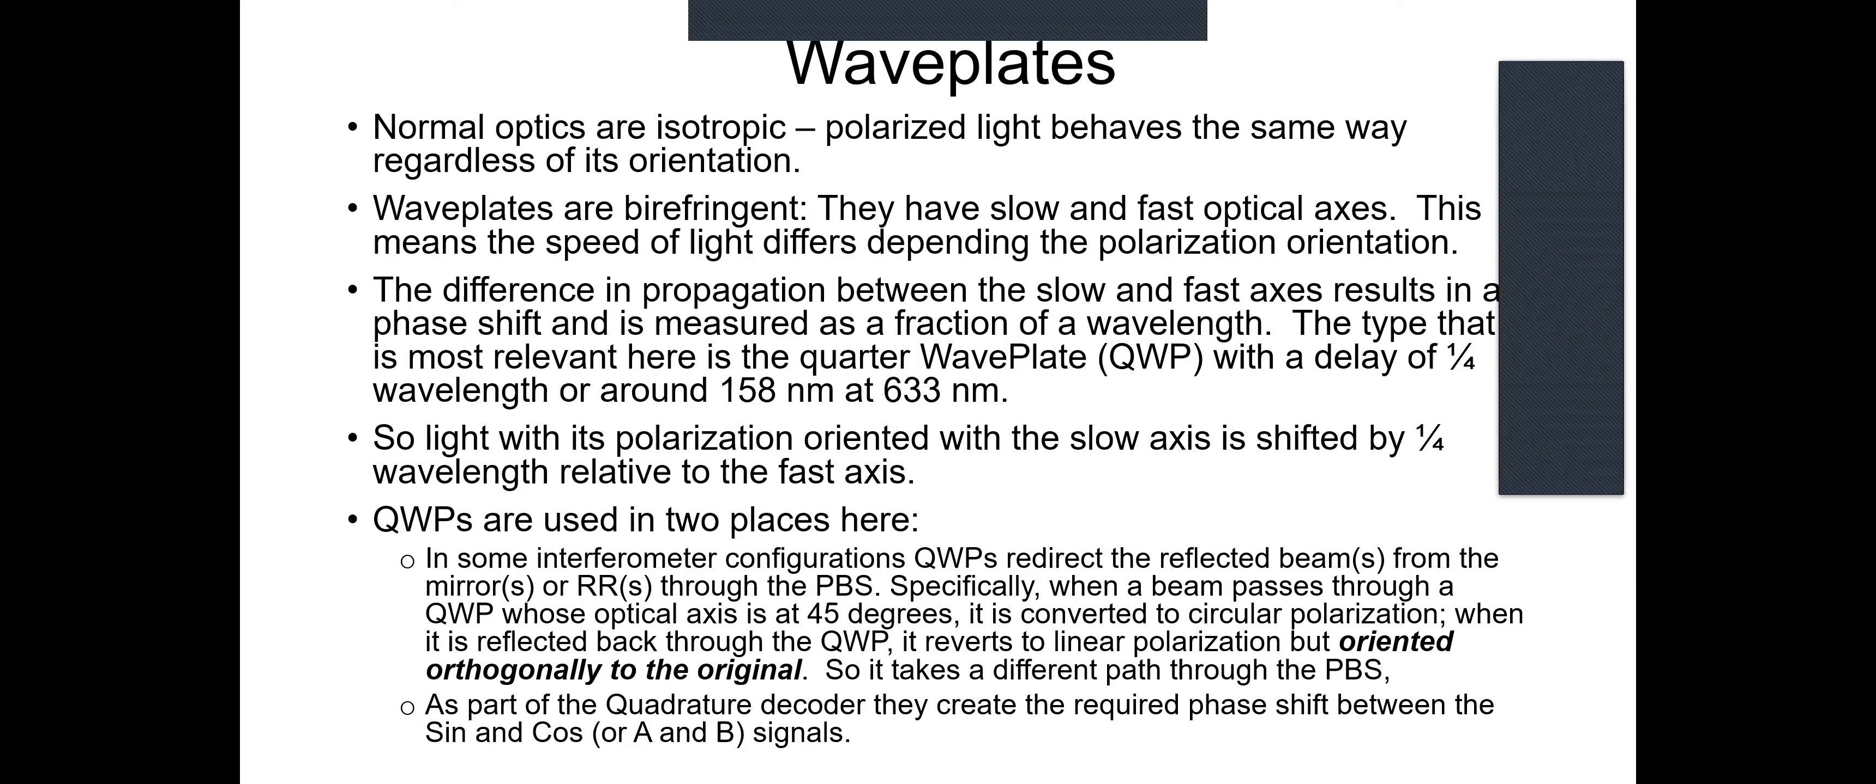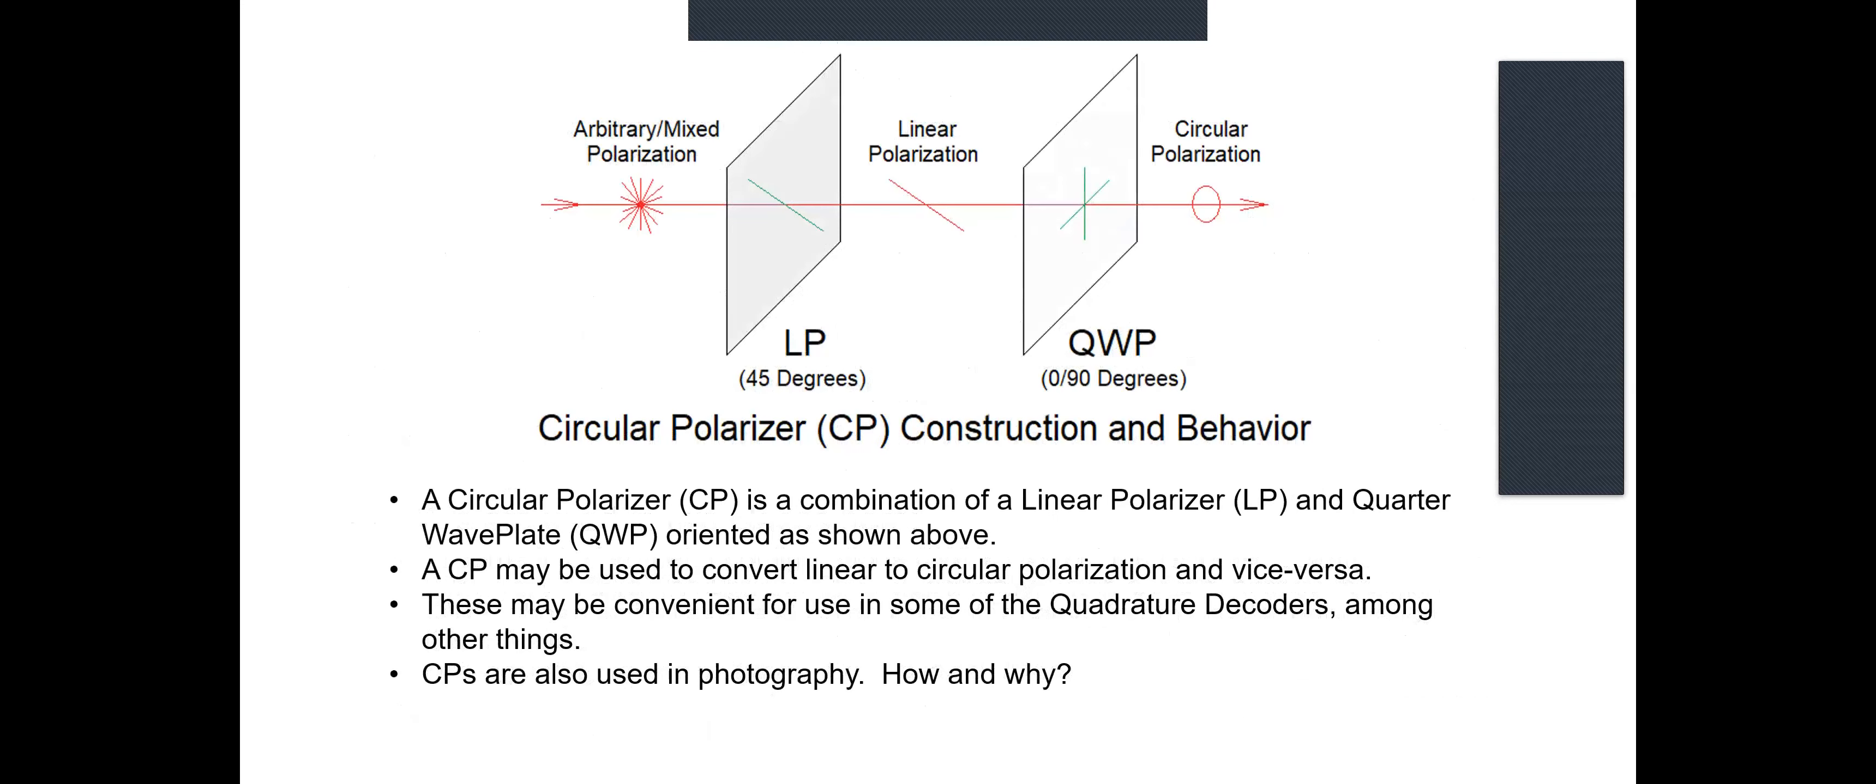Quarter wave plates are used in two places here. In some interferometer configurations like the one you will be using, they redirect the return beams from the mirrors or retro-reflectors through the PBS so that they take a different optical path. As part of the quadrature decoder, they also create the required phase shift between the two signals, the sine, cosine, or A and B signals. The circular polarizer, which was described before, is simply a linear polarizer oriented at 45 degrees followed by a quarter wave plate oriented at zero degrees. These are also used in photography - anybody here who's a photographer probably has used a circular polarizer on their camera.